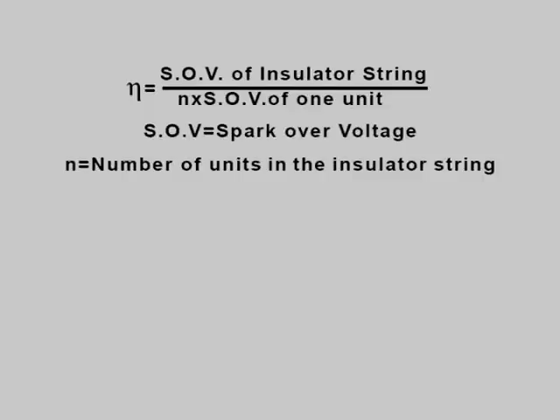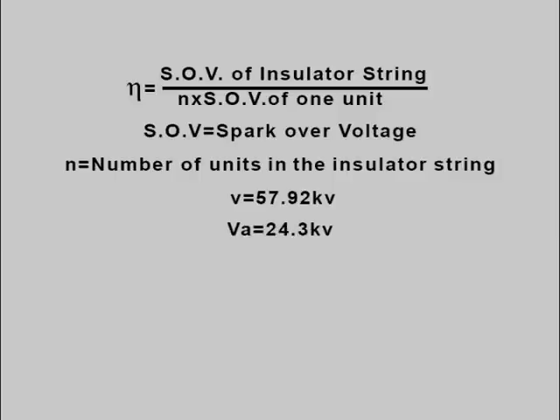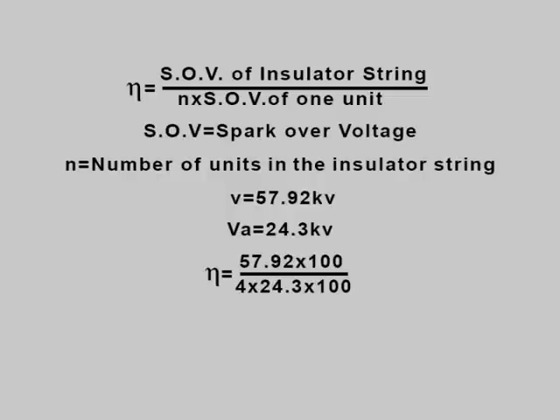We will substitute the value of SOV of the insulator string. The value of V is equal to 57.92 kilovolt, and the value of spark over voltage of 1 unit is 24.3. Then substitute the values of V and VA in that formula. Then eta is equal to 57.92 into 100 upon 4, the number of units in the insulator string, multiplied by 24.3 into 100.